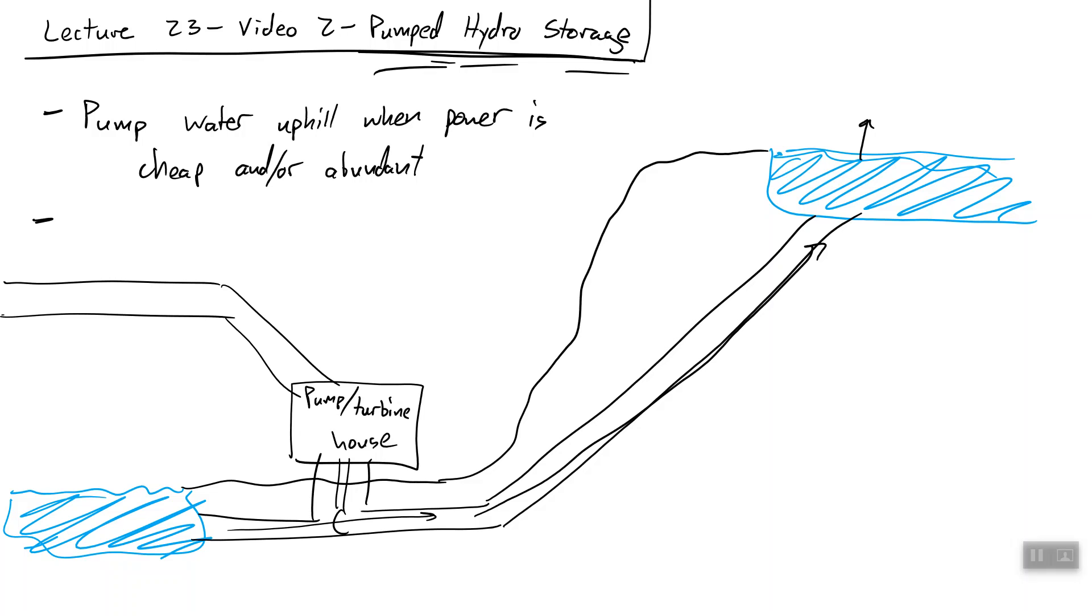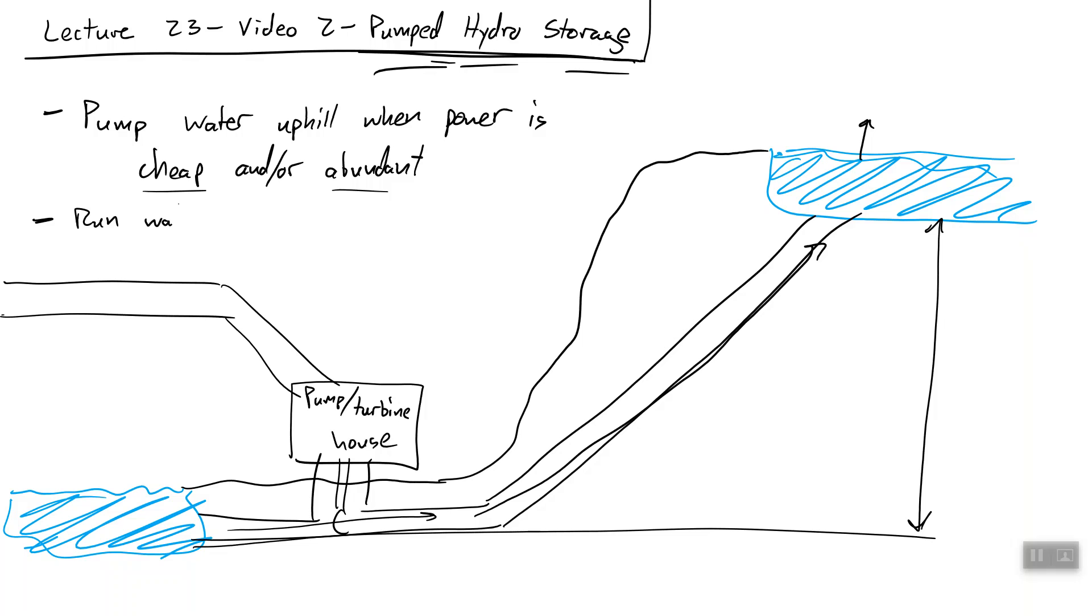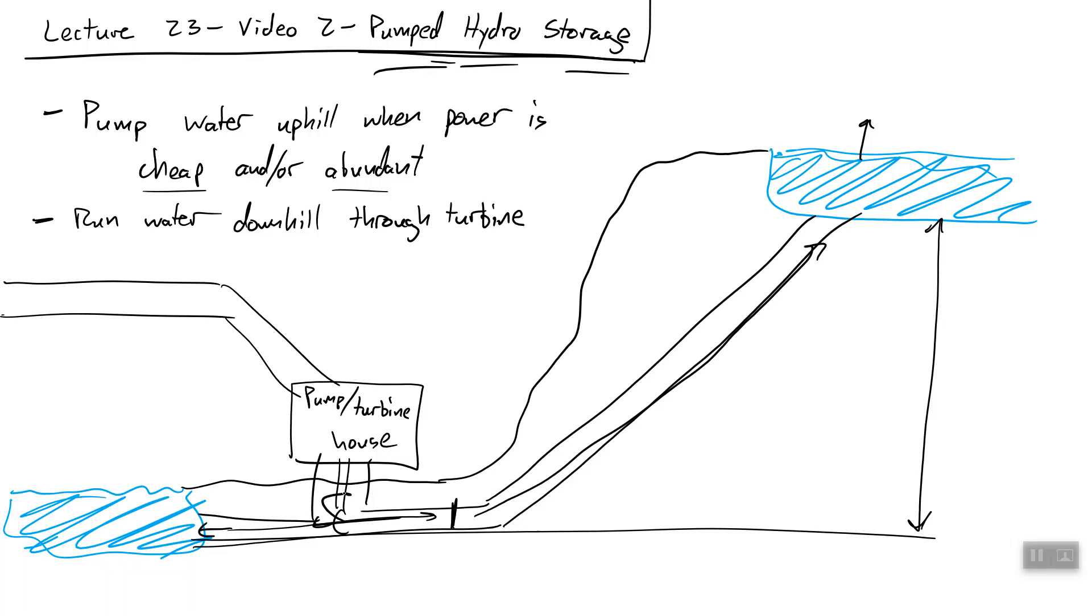Now we sit and wait. We have stored a weight above ground. We now have gravitational potential energy that we didn't have before. And then, as soon as power becomes either not cheap or not abundant, then we run that water downhill. We essentially open a valve right here and allow that water to flow back into our reservoir, which it will do because it is higher up. It's got this pressure pushing it down and into this reservoir. We run it downhill, but we're going to run it through a turbine, usually the same piece of material that we use to pump the water uphill. We allow it to run back through that turbine and turn it the opposite direction. And then the motor powering our pump now becomes a generator, and it generates electricity and sends it back along the power lines to be used in the grid.